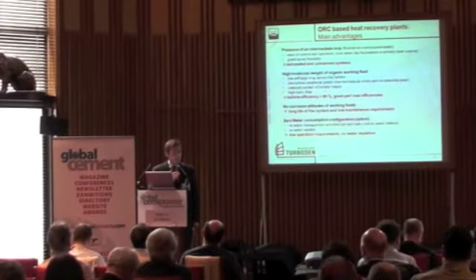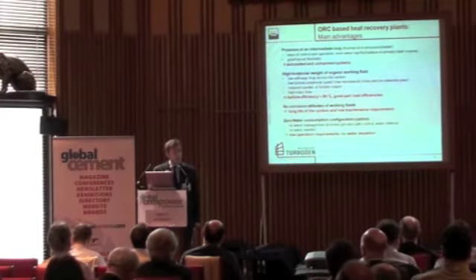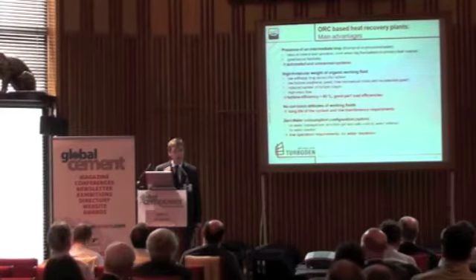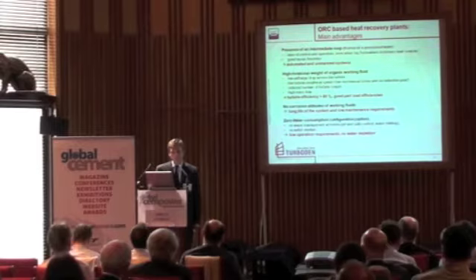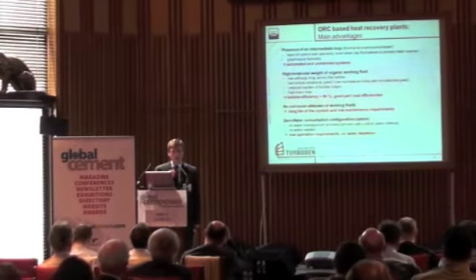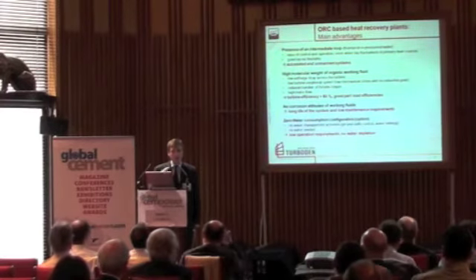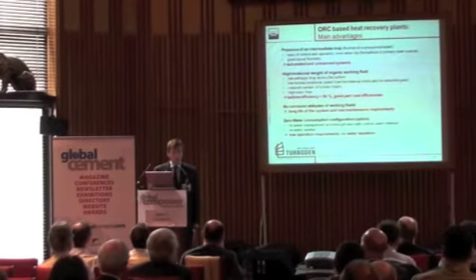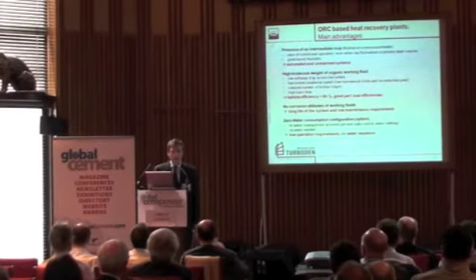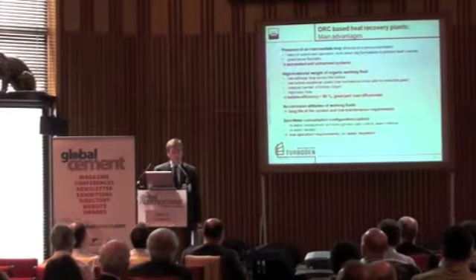Turbine efficiency for an ORC plant starts from 80% and may achieve even 90%. In steam plants, typically 80% is an arrival point for 10 megawatt size plants. We don't have water in the cycle, so there is no corrosion of the working media. This makes the system have a long life. And we can set up the plant for a zero water consumption configuration, avoiding any water management activities, and potentially employ the plant even where no water is available.